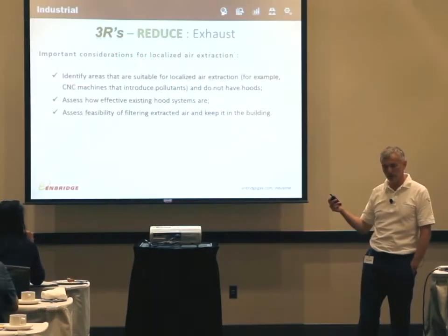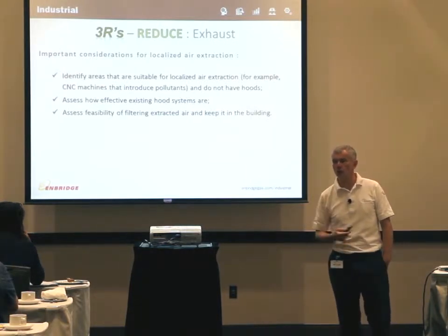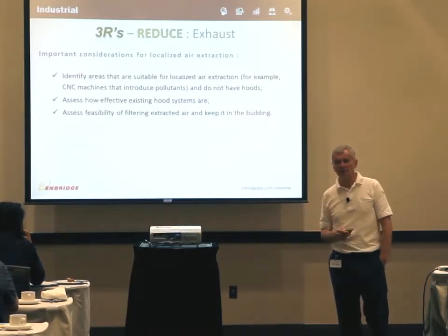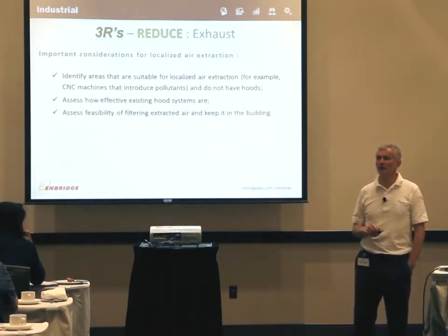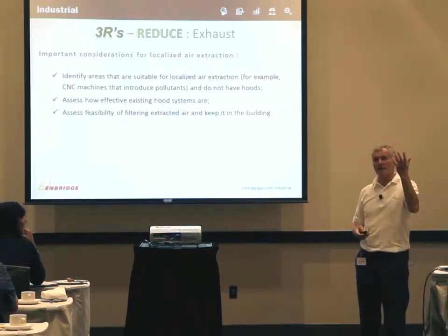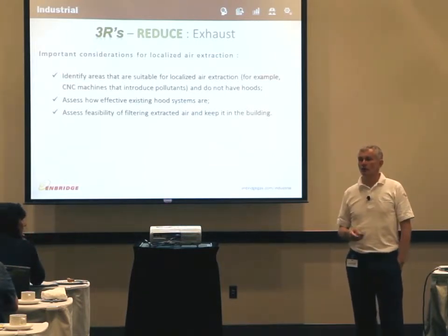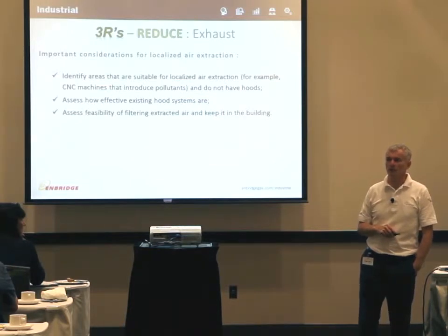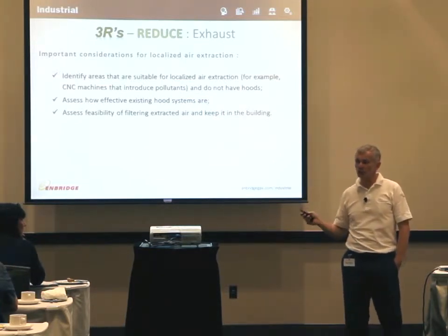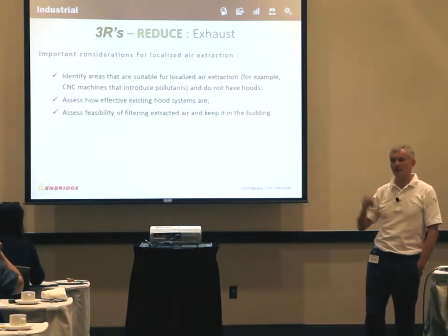In the same facility, we had a quench line. When we made a coil to put it to quench, we had a localized fume exhaust. At least 3-4 times a year, we had a local fire in the chimney, because that was all oil that got pulled by the fan, and eventually, if it wasn't cleaned, it started a fire. So that was our signal: let's clean the chimney. But if you don't have such an environment, the chimney will get clogged up. You will not get good extraction out of the hood, and you will think you need extra exhaust on the roof.